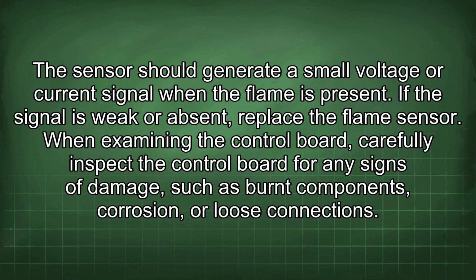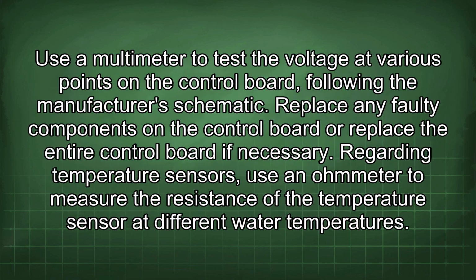When examining the control board, carefully inspect the control board for any signs of damage, such as burnt components, corrosion, or loose connections. Use a multimeter to test the voltage at various points on the control board, following the manufacturer's schematic. Replace any faulty components on the control board or replace the entire control board if necessary.